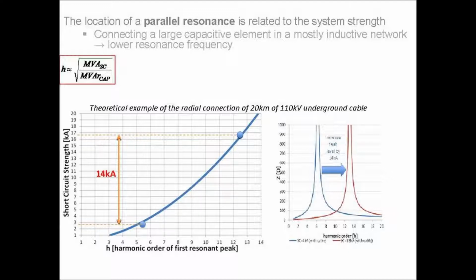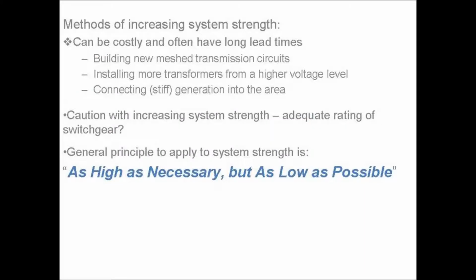So supposing we were to increase the system strength in that area by maybe adding a new transformer or meshing the node further, bringing new lines to it or whatever. We need to increase it by like 14 kA just to shift it back up to the 12, 13, 14 harmonic range, which is a significant increase in short circuit currents. So basically, how do you do that? I already mentioned you can bring new transmission circuits, install higher voltage transformers, or else connect stiff generation to the area, so CCGT or something like that might need to come in order to increase it up.